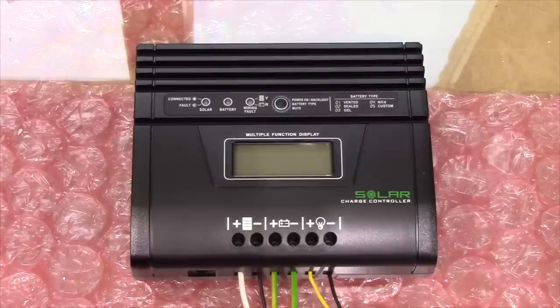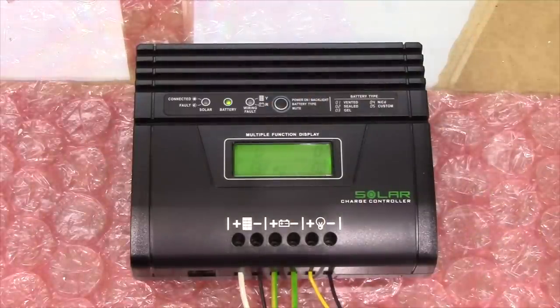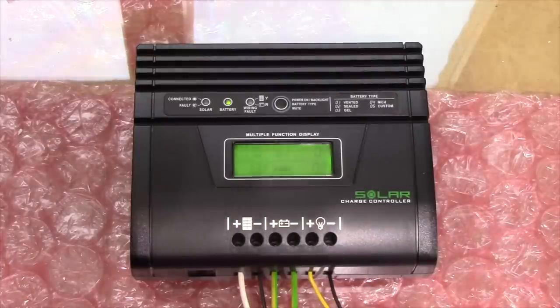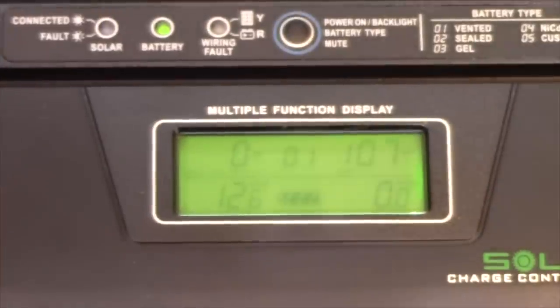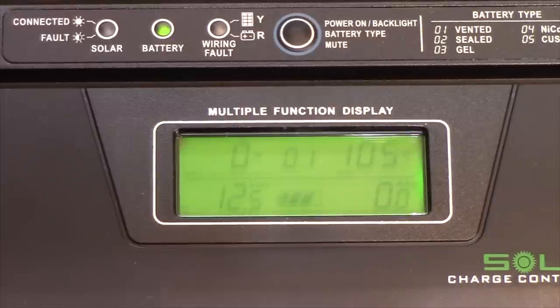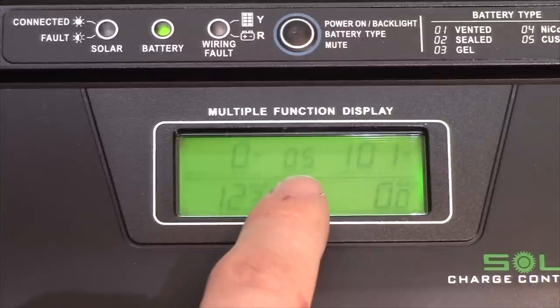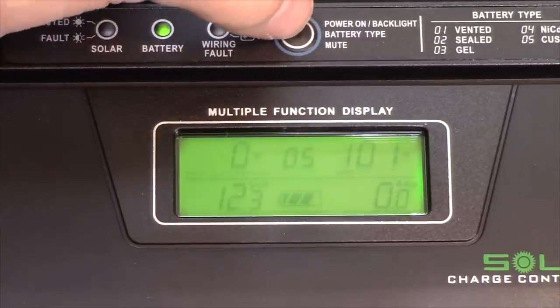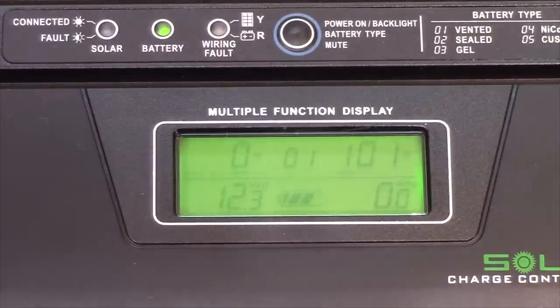So, I'm assuming that feature just isn't implemented yet. As for the predefined battery settings, you do get pretty good settings for the lead acid batteries anyway. You get 14.3 volts bulk charge and you get to choose between 13.2, 13.4 and 13.7 volts float charge. So, that should be pretty sufficient for most lead acid battery systems.